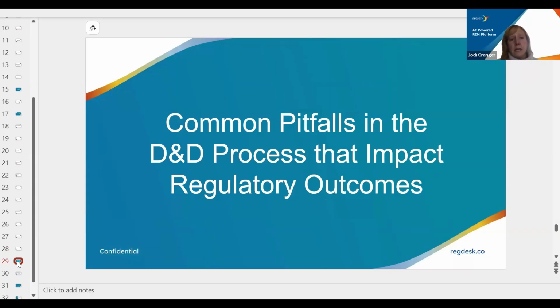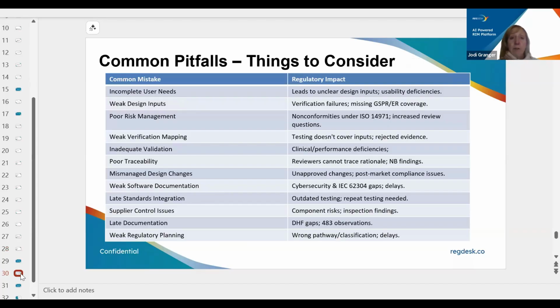So, common pitfalls in the design and development process that impact regulatory outcomes. There are many common pitfalls, and I've just listed a few in this table that will be provided. The first is incomplete user needs. Not having a clear understanding of what the customers, ultimately the clinicians, are going to need can result in unclear design inputs or usability deficiencies. As an example, if you have a product that's packaged in a Tyvek pouch, and the way you open that pouch causes the product to pop out and go outside the sterile field, that's a user requirement. If you missed it, you could fail during your user assessment, your usability testing.